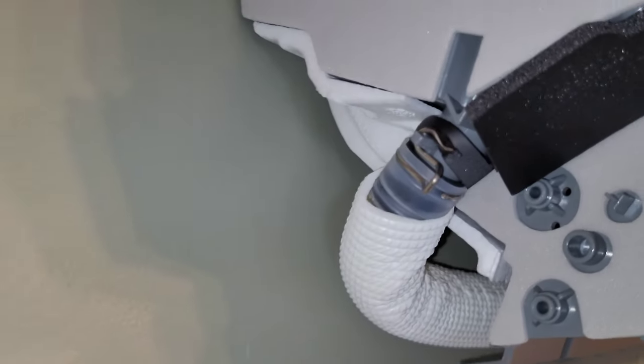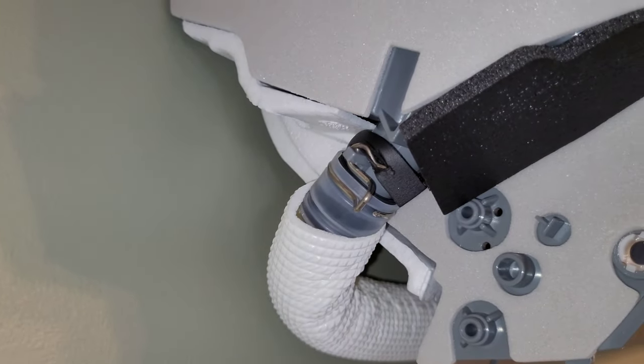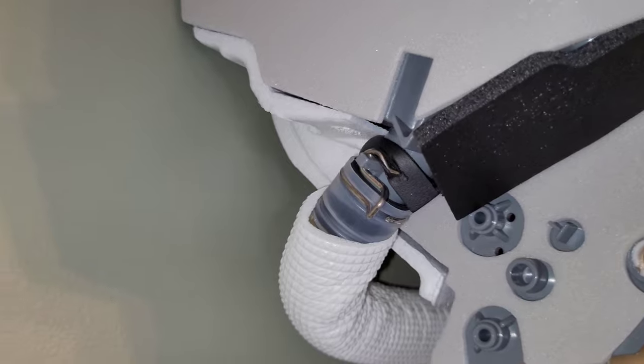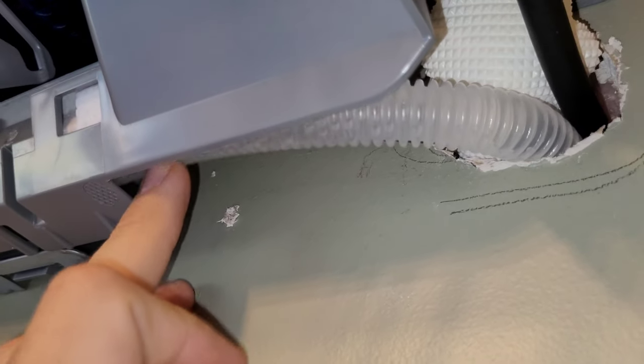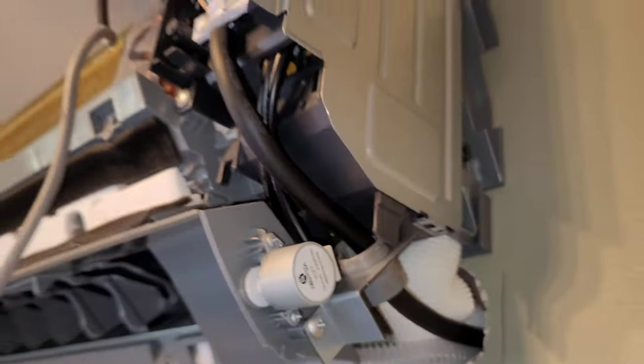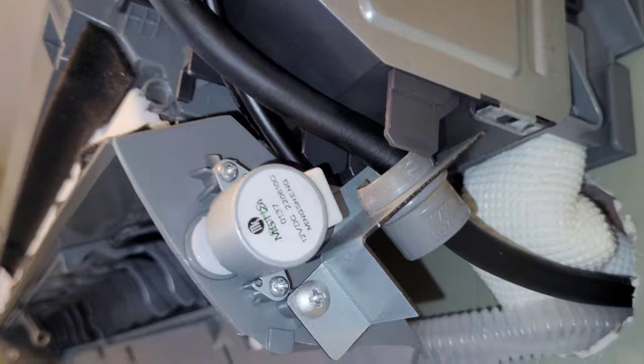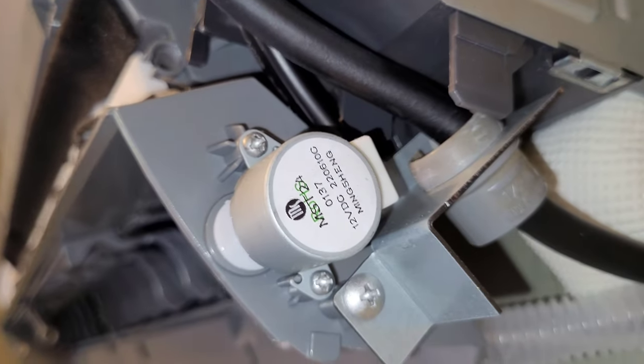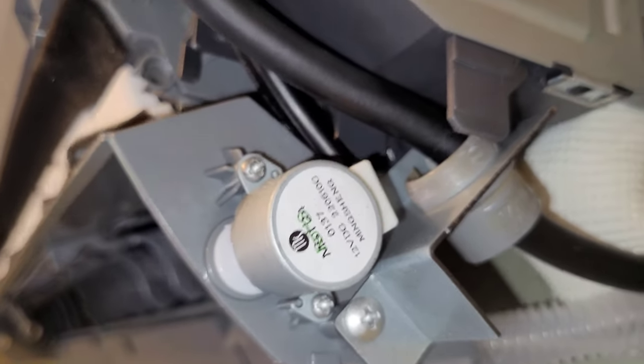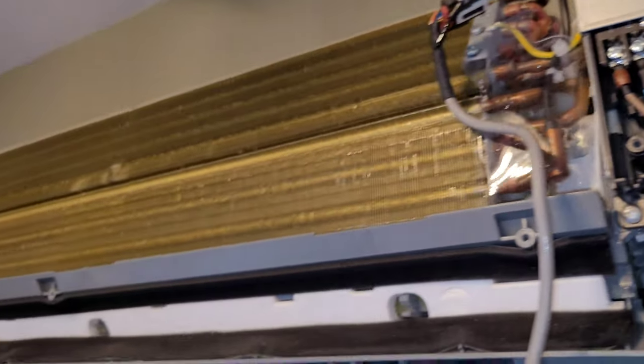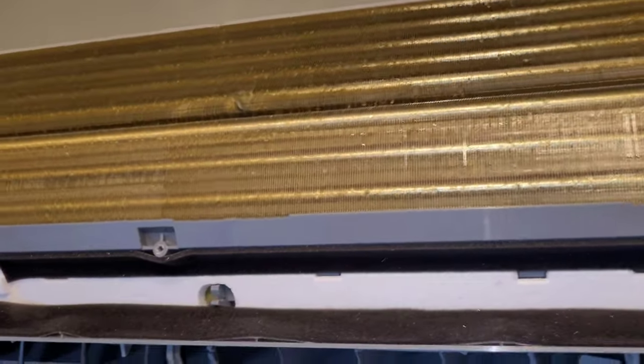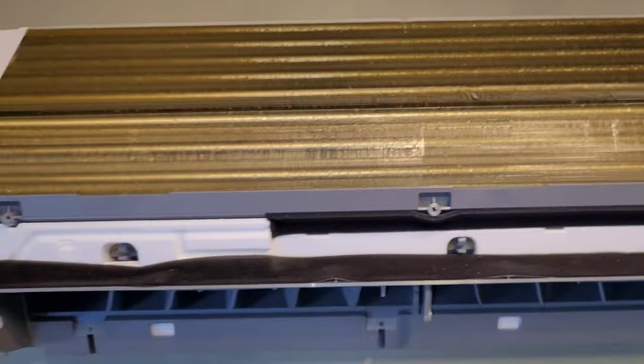But it's also a good time to have a look at your drain. I was in a big rush when I installed this thing and I didn't switch the drain to the appropriate side, so my drain actually runs across the whole back of the unit and out the hole in the wall. I could have drained it on this side, but I didn't. Not a huge deal because I'm going to be keeping up on my maintenance. But if you don't keep up on the maintenance, that drain can get sludgy and cause blockages. It can cause a leak in your indoor space and obviously you don't want that. That's our little stepper motor that controls the louvers. Our circuit board is behind that panel there. Overall, once again, a very standard mini split.